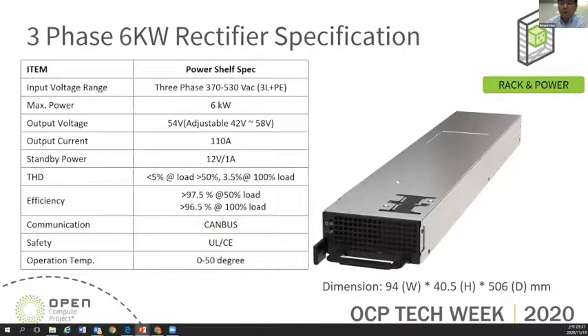So according to the previous page analysis, we find a 3-phase rectifier is more flexible. So we determined to develop a 3-phase product for next generation data center applications. So here is the spec for that. The input voltage range is 370 volt to 530 volt, 6 kilowatt for the power module, and the output voltage is 54 volt, but it is adjustable from 42 to 58 volt. For the efficiency and THD, we put a very high target here, and this is the dimension here. Based on this design, we can achieve higher than 50 watt per cubic inch for the power density.